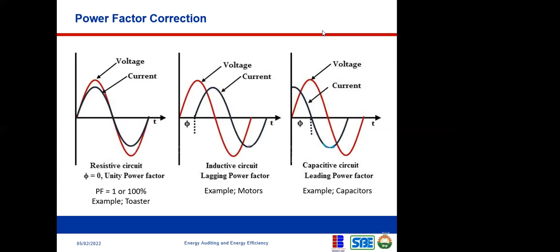To know the size of kVAR, the reactive power, needed to correct the power factor problem, you need to know the real power you're actually consuming, then multiply that by a table factor. There is a standard table factor you can find online, and I will show us one in this training.